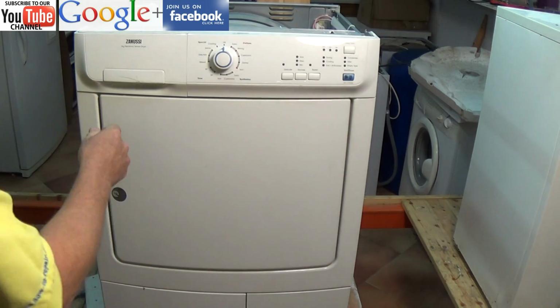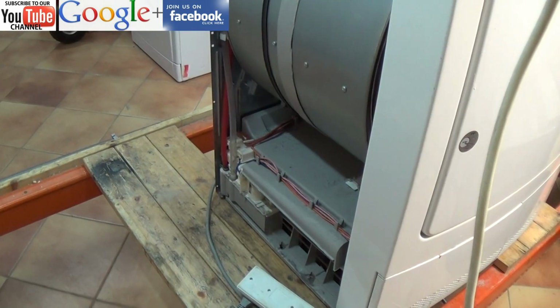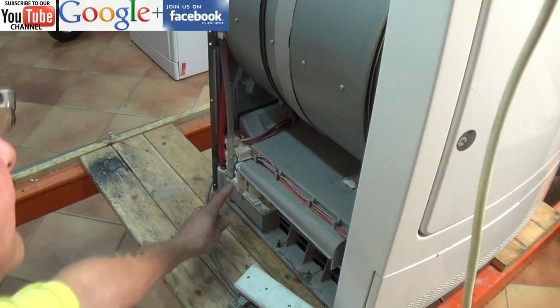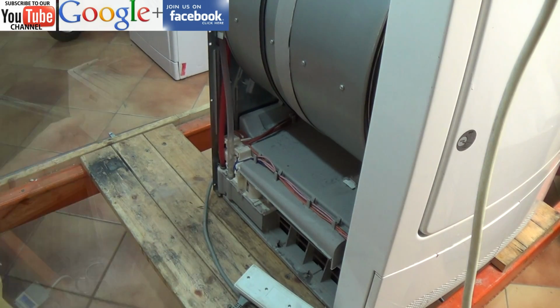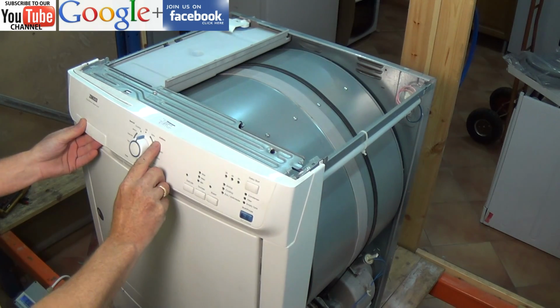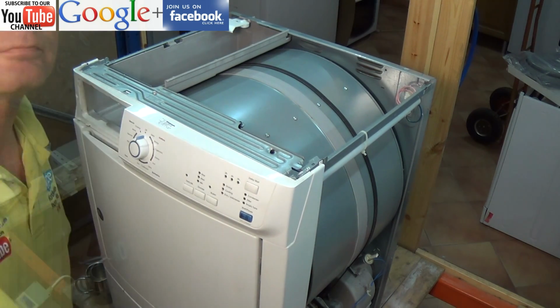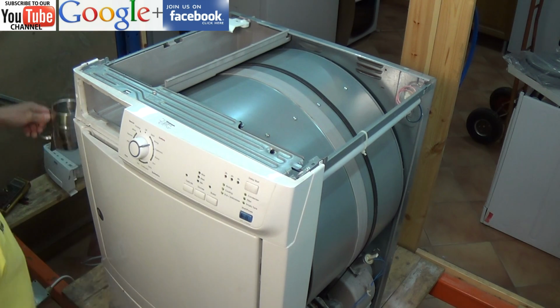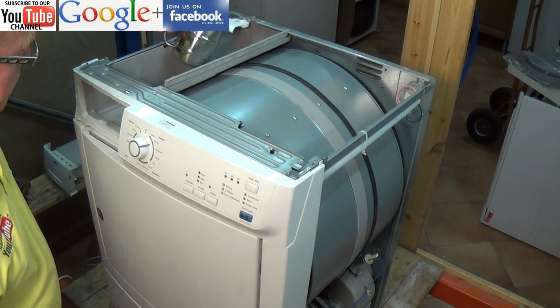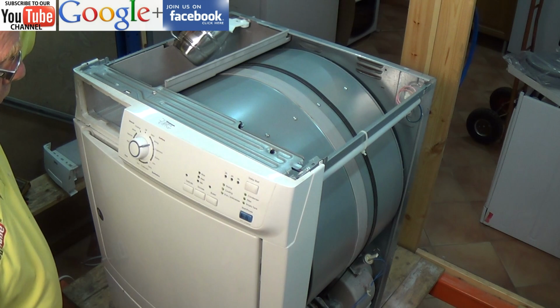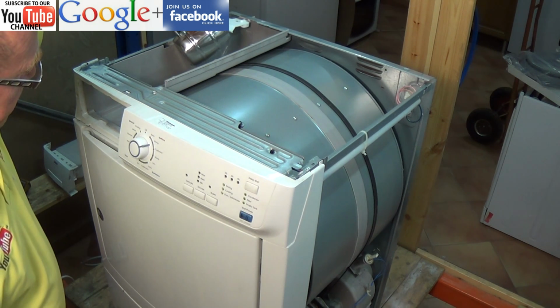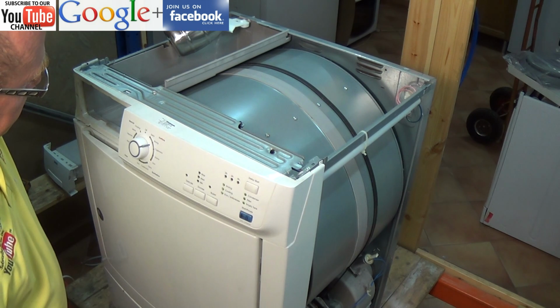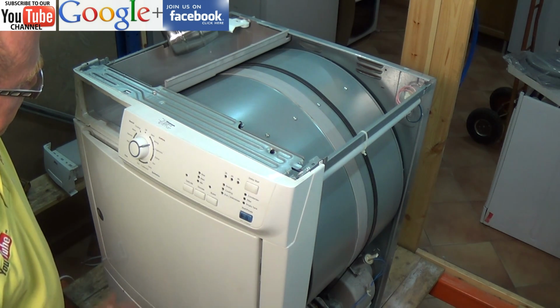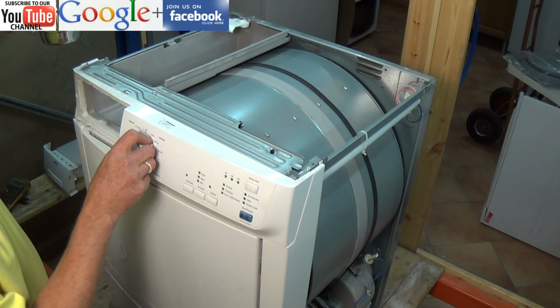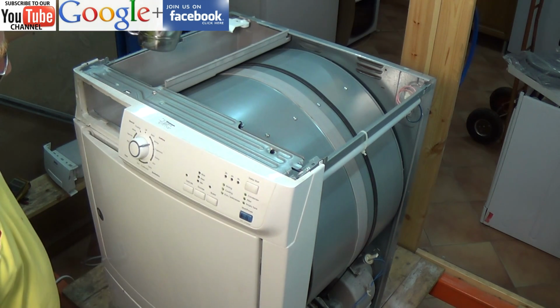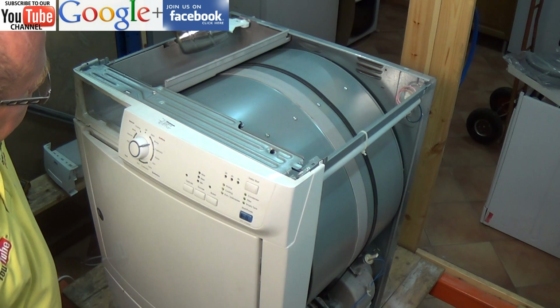Now we're doing test number 2, which is the pump on the circuit board type, or fascia panel type, sorry, and we'll be checking the switch at the bottom. It's a float switch, and this will activate the motor. Now we need to pour about 0.7 of a litre of water into the bottom reservoir, so I'm just filling from the top reservoir and letting it flow back down. Make sure it's empty before you start pouring the water, and I'm just turning the dial back onto 2 so it doesn't time out.